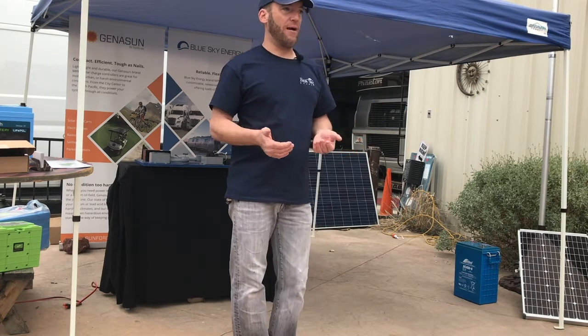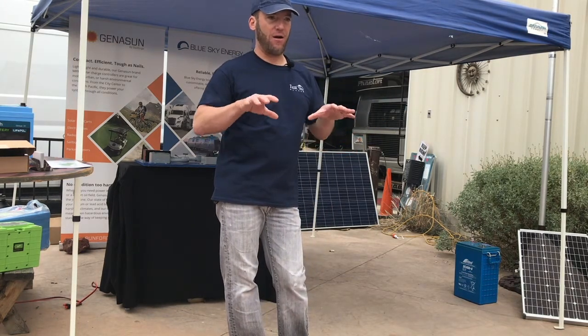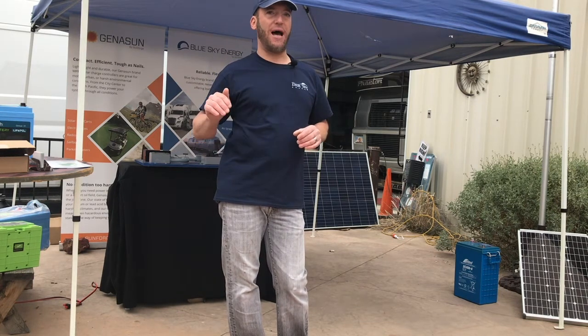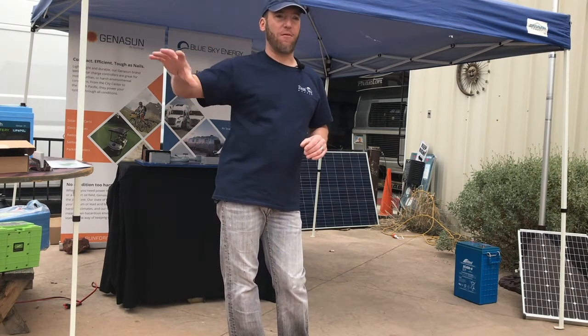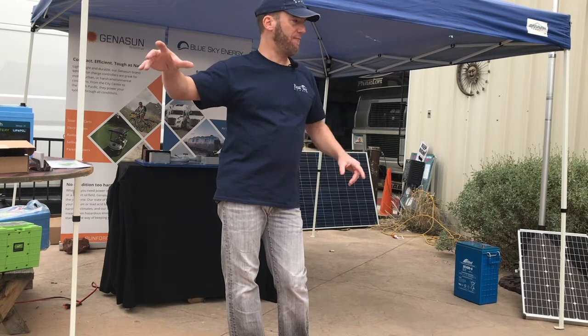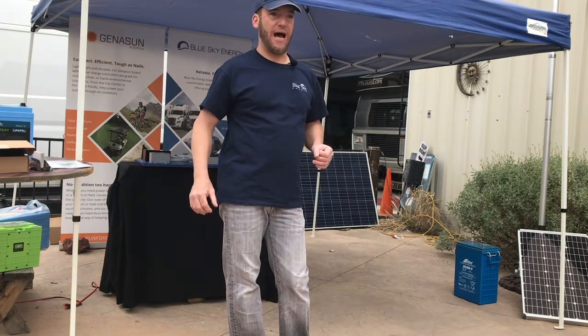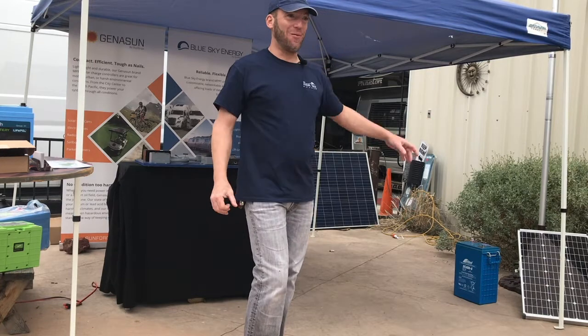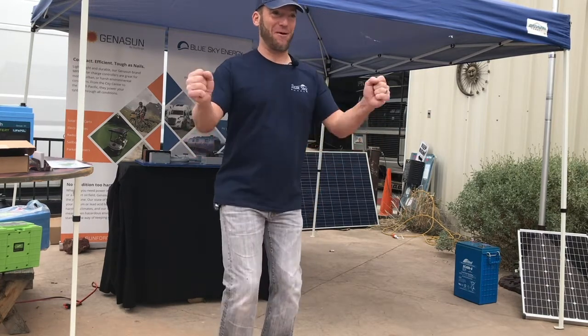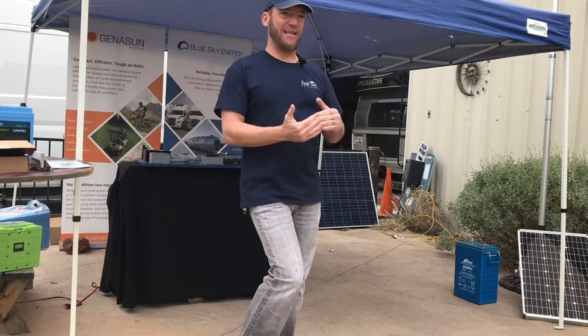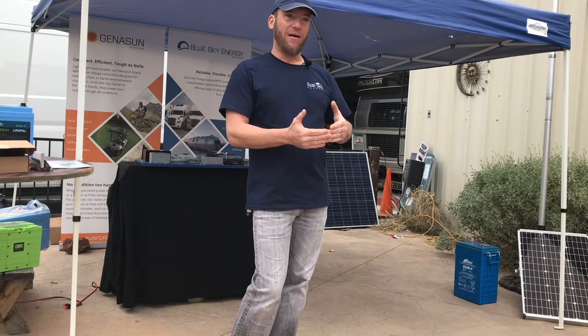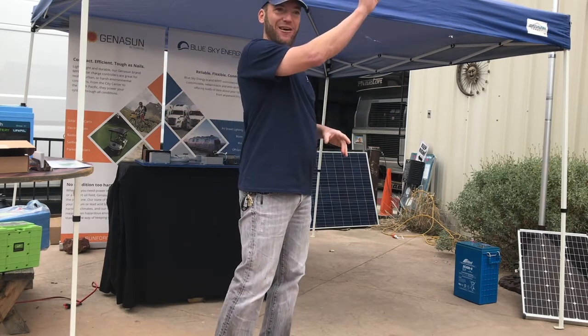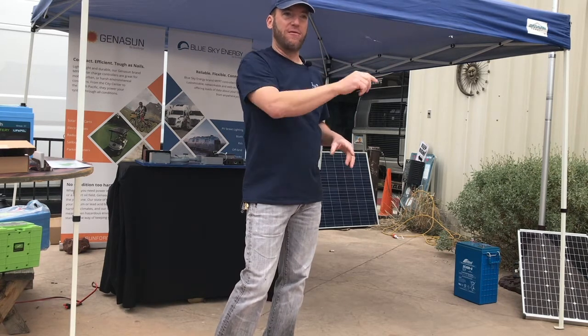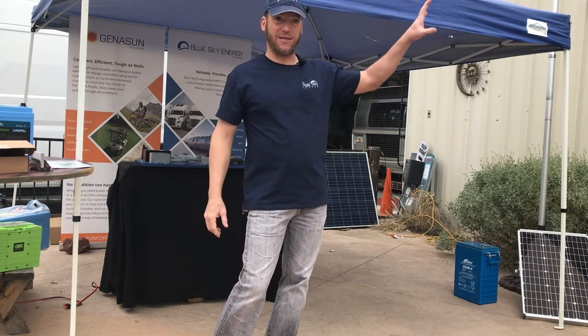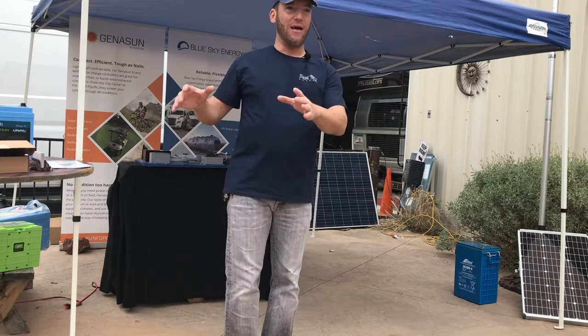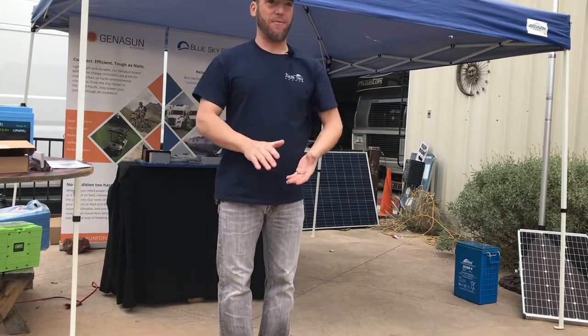The only time I normally recommend anti-reverse or blocking diodes in a parallel system is situations where people have panels on their roof and also have a remote system, like a foldable ZAMP system or something like that. The reason they got this is so when they park under a tree, they can still run out and put this panel out. Now, if all that's connected into the same system in parallel, the remote is going to try to feed in, and you're going to get a draw on your roof panel. So they'd rather take a 5% hit on the roof all the time, but when they park under a tree, they can have the remote panels still hooked up to the same charge controller.